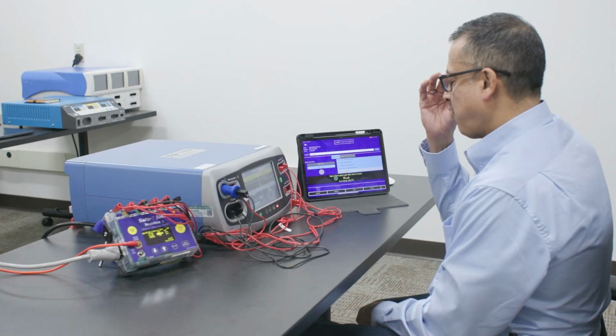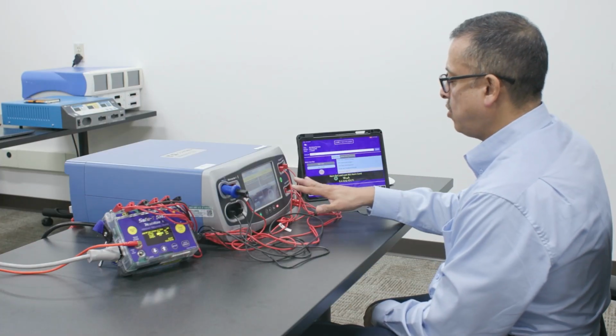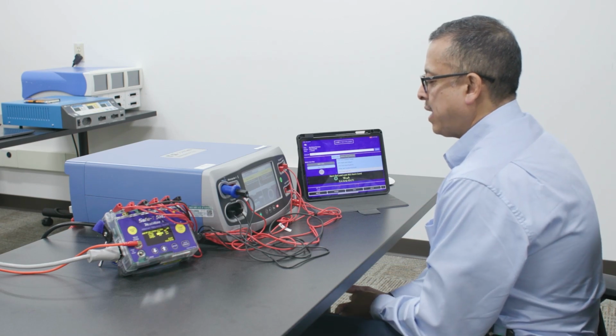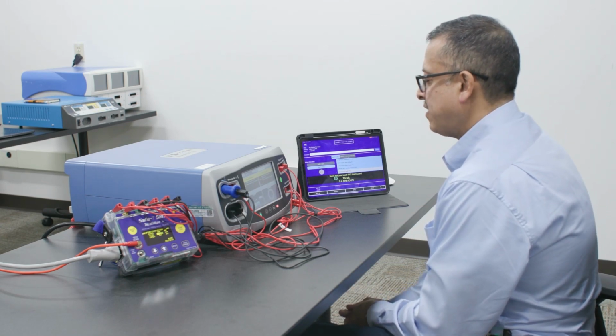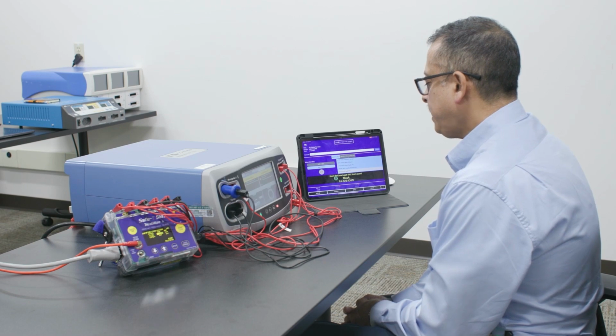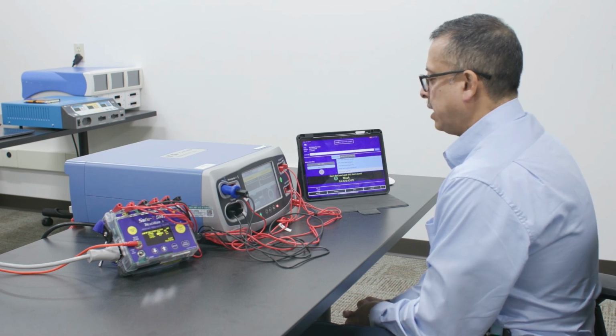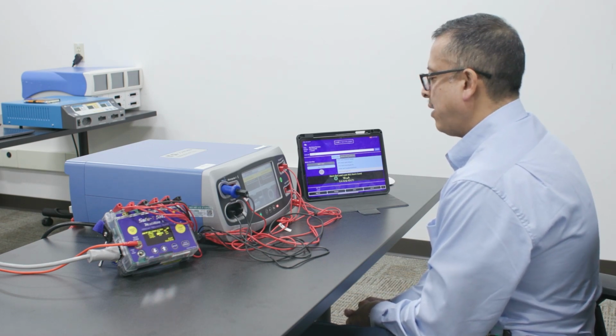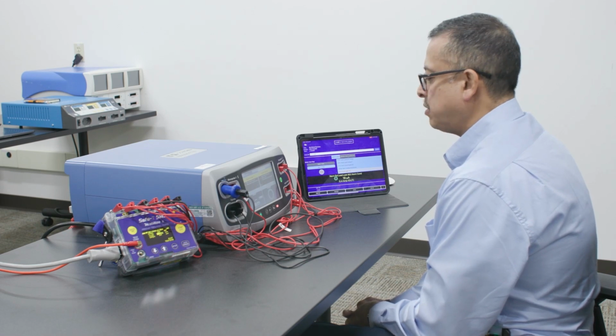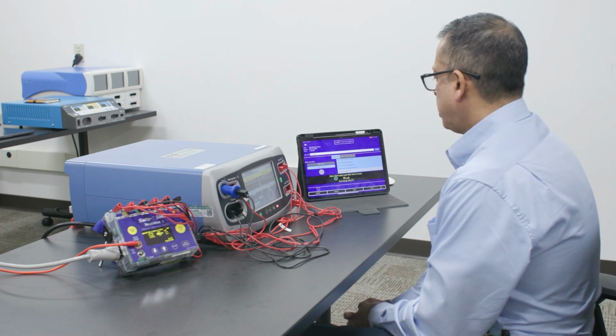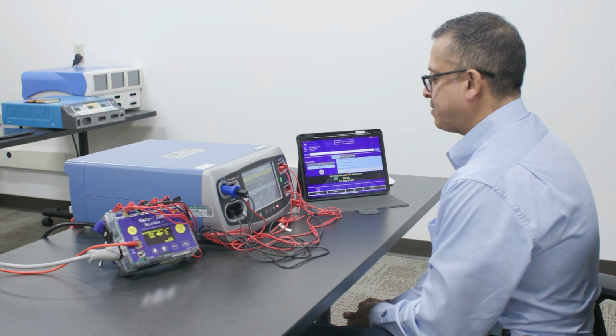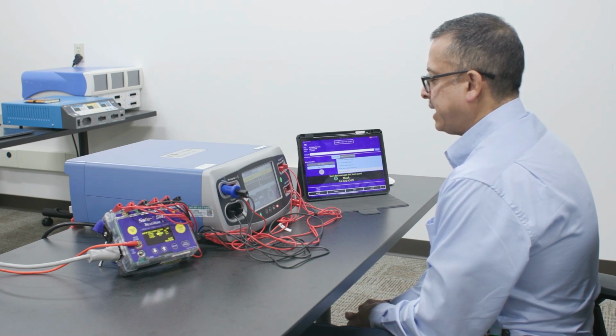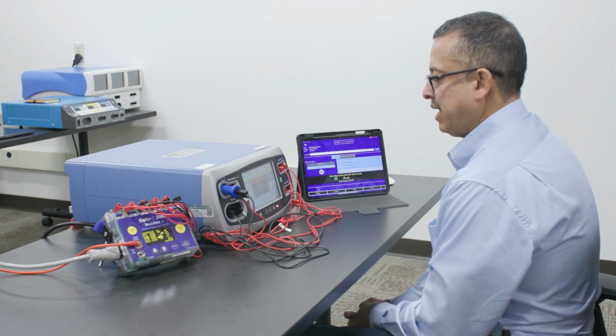And it's performing a lead leakage test in every single output port, making sure that it meets the manufacturer's requirements for that test. And again, these tests are running a little bit longer because we're allowing that ESU unit to boot up completely. So you're going to run through all these tests and make sure we've captured all of the results and that they're within the manufacturer's specifications.